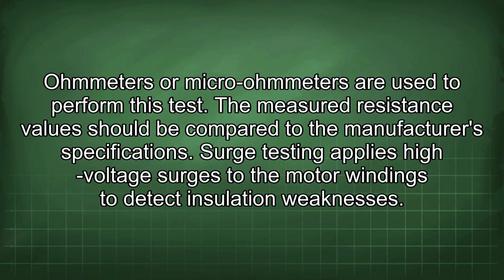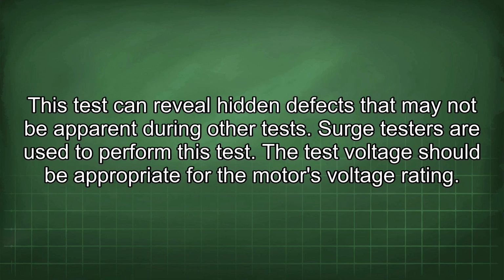Surge testing applies high voltage surges to the motor windings to detect insulation weaknesses. This test can reveal hidden defects that may not be apparent during other tests. Surge testers are used to perform this test. The test voltage should be appropriate for the motor's voltage rating.